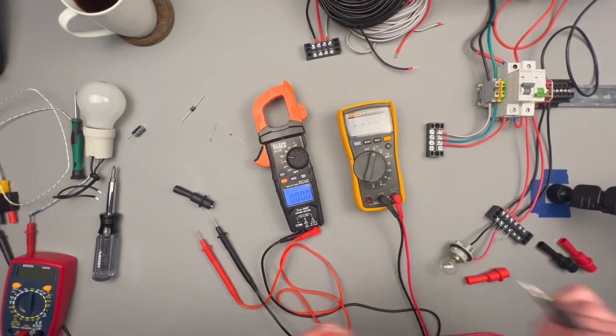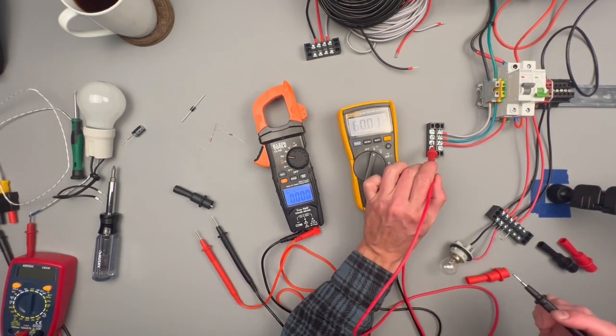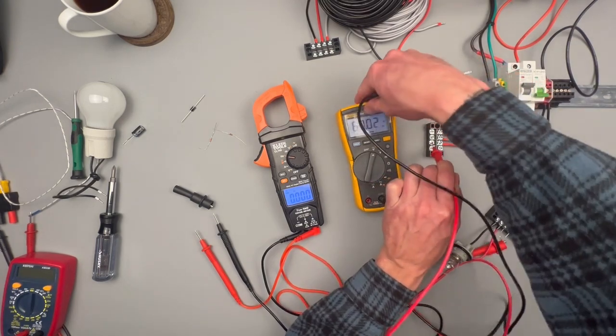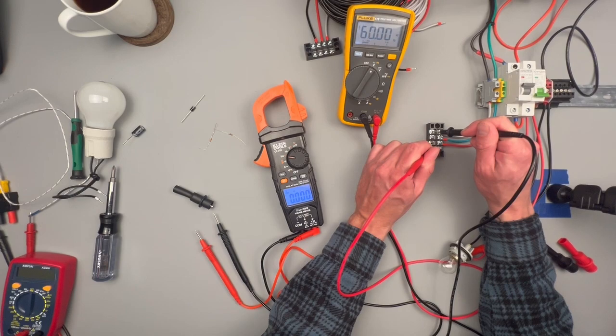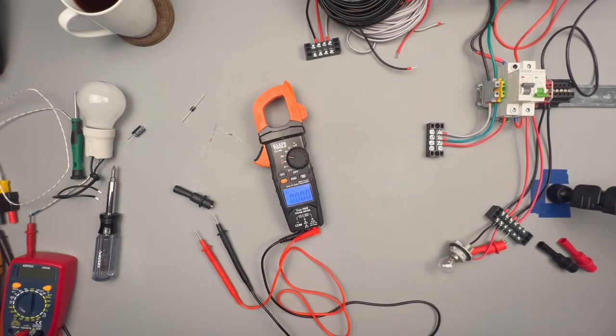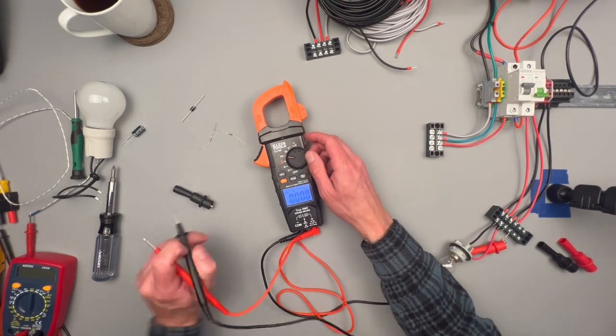As opposed to if I take this Fluke, I put it on a Hertz setting. I do a single probe. I come back with 60 Hertz. I use both probes. I still come back with 60 Hertz. So that's something to look out for on this meter. It doesn't have a way to compensate for that.